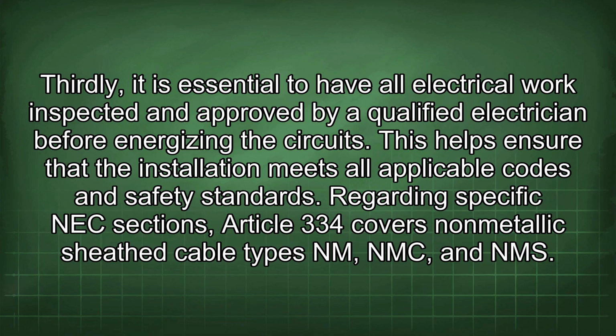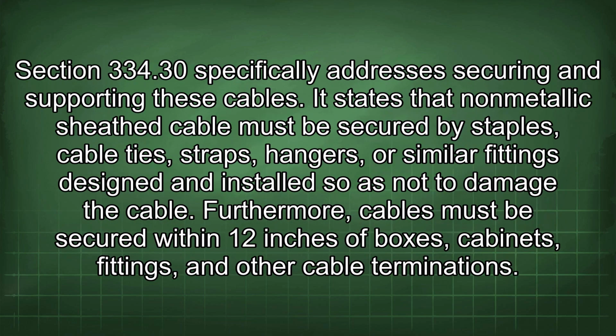Regarding specific NEC sections, Article 334 covers non-metallic sheath cable types NM, NMC, and NMS. Section 334.30 specifically addresses securing and supporting these cables. It states that non-metallic sheath cable must be secured by staples, cable ties, straps, hangers, or similar fittings designed and installed so as not to damage the cable. Furthermore, cables must be secured within 12 inches of boxes, cabinets, fittings, and other cable terminations.